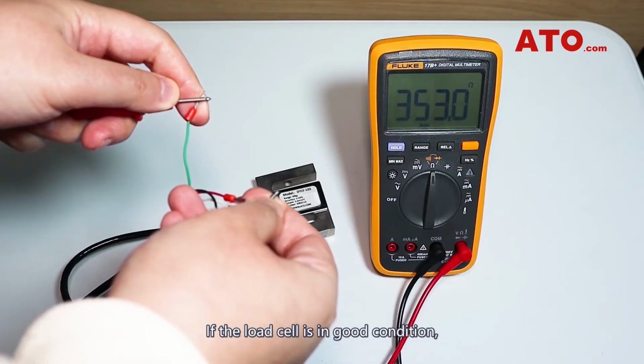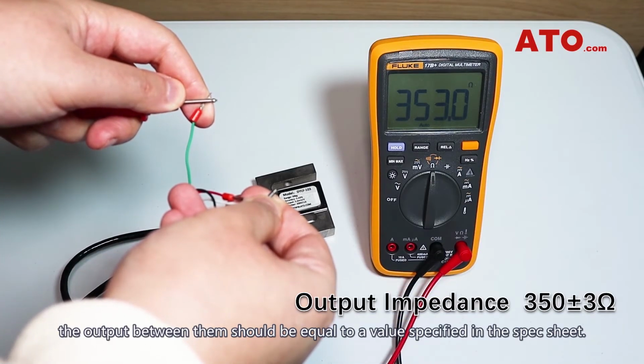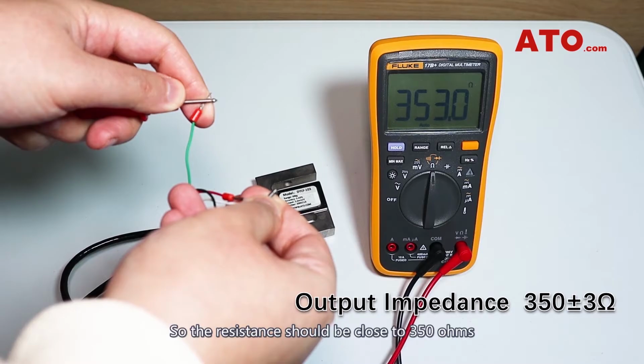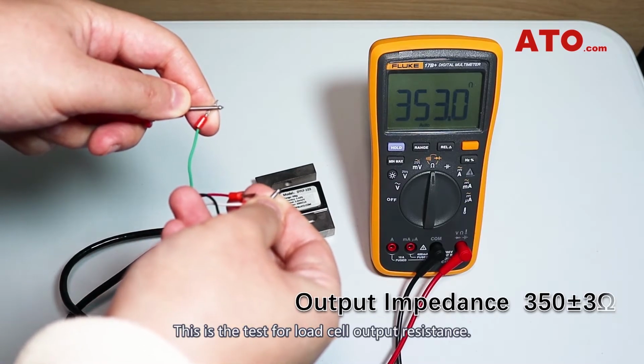If the load cell is in good condition, the output between them should be equal to the value specified in the spec sheet. So the resistance should be close to 350 ohms, and we get a reading of 353 ohms. That's fairly close enough. This is the test for load cell output resistance.